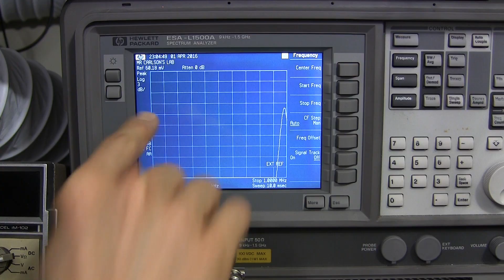The spectrum analyzer is now set up to look at the bottom end useful range of this RF active probe. The start frequency is at 50 kilohertz, and the stop frequency is at 1 megahertz, at the edge of the screen there. Again, we want to keep this within this string of boxes here. We'll consider this line here the 3 dB down point. So I'll roll the signal generator right now and bring it to that point. I'd say that's about the bottom end, and that's at 390 kilohertz.